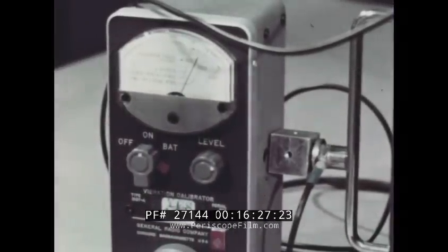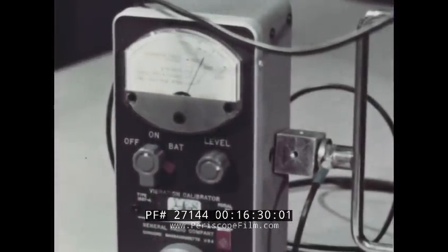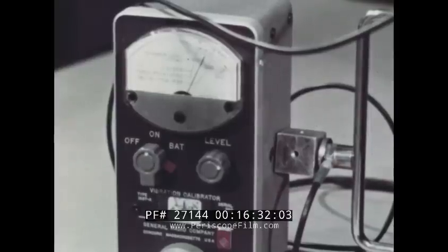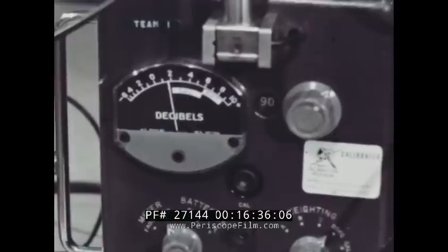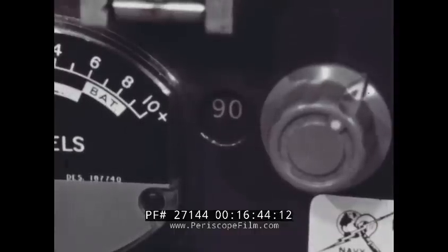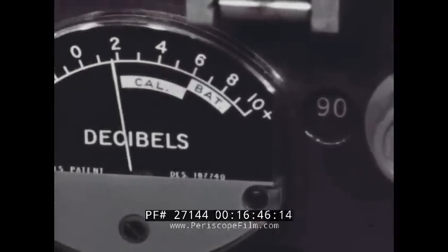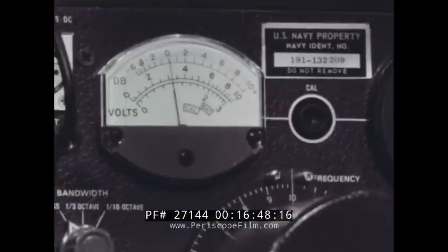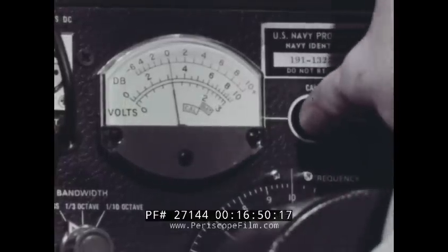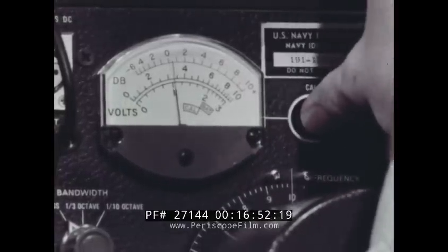The vibrator is on, and the sound level meter has been adjusted to give the prescribed reading for the type of pickup in use. In this case, it's an attenuator setting of 90 and a meter reading of 1.7. Adjust the analyzer to give the same meter reading, 1.7.